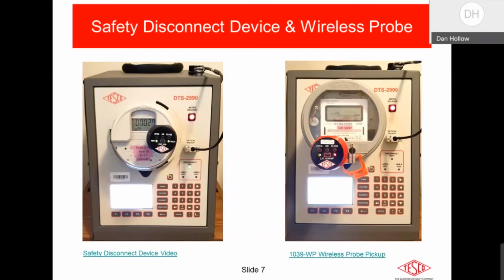I'm going to show you a device that is using the optical port on the meter. It is not an optical pickup or an optical probe. It is unique in the industry to my knowledge. The device you see on the unit on the left, on that Aclara meter, is called a safety disconnect device. It uses the optical port on the meter. And this particular device's sole purpose is to open or close the service disconnect switch inside of a meter.